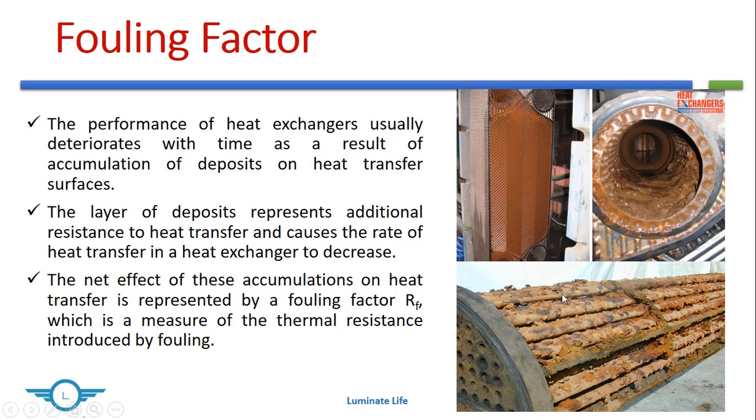Now when a heat exchanger is put into service, we can say that there is no sedimentation, but over time sedimentation will develop. So while designing a heat exchanger, we need to account for the resistance which the sedimentation induces. To account for that resistance offered by the sediments, we introduce a factor called the fouling factor, or RF.